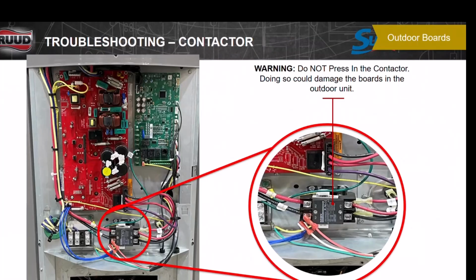Okay, so next here we've got this. How many times have I said this today? Don't push the button. Do we ever push the contactor in? No, we do not, because we'll let the magic smoke out, and there's no smoke boxes available to put it back. It's impossible to put it back. So we never want to push the contactor in because that makes a direct short.